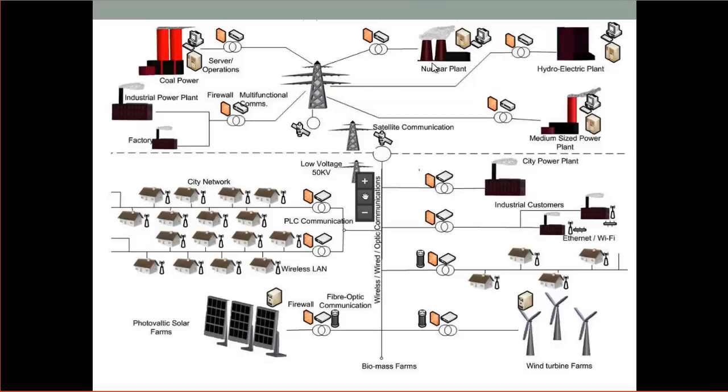You got to pay those bonds off. But you can tell a nuclear plant, I need you to make 1,000 megawatts, or I need you to make 2,000 megawatts, and it'll make that. And maybe every other year you take it offline for a couple of months in the spring or the fall to do maintenance on it. But for the most part, it makes power when you tell it to make power. Same thing for your coal plant. And then you have the little gas turbines. The neat thing about a gas turbine, it's like a big jet engine with a generator on it. You can push a button, and in 15 minutes you can be making 150 megawatts.